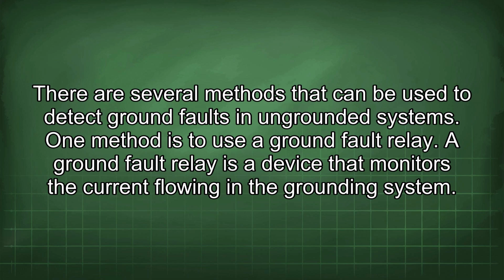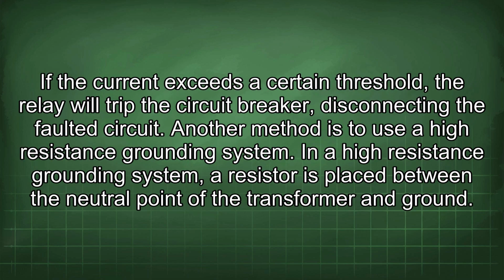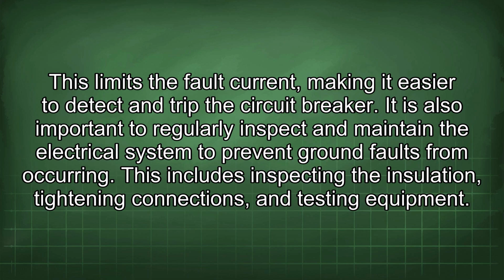One method is to use a ground fault relay. A ground fault relay is a device that monitors the current flowing in the grounding system. If the current exceeds a certain threshold, the relay will trip the circuit breaker, disconnecting the faulted circuit. Another method is to use a high-resistance grounding system. In a high-resistance grounding system, a resistor is placed between the neutral point of the transformer and ground. This limits the fault current, making it easier to detect and trip the circuit breaker.